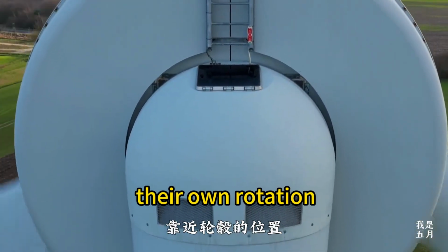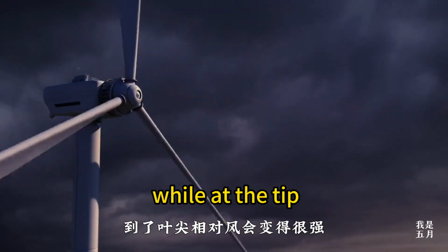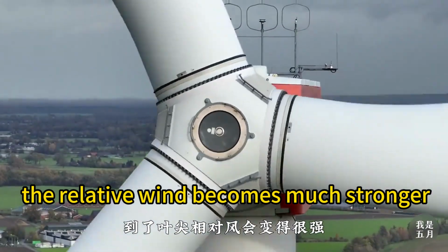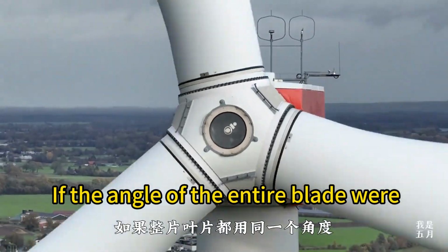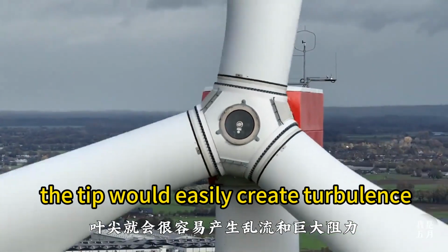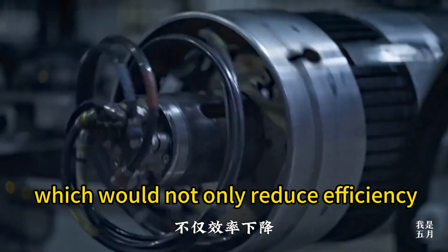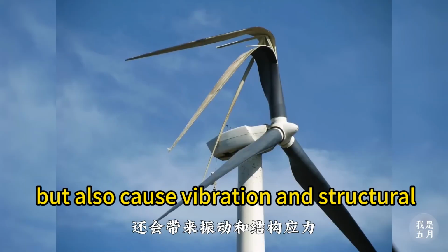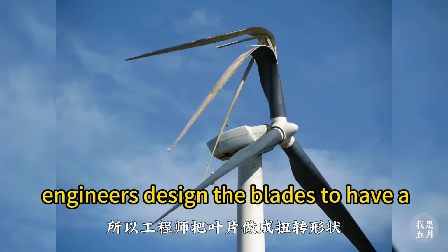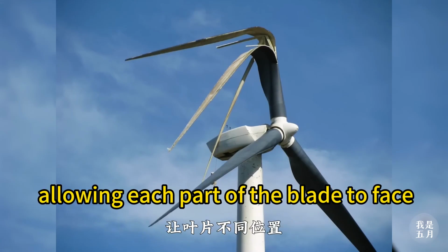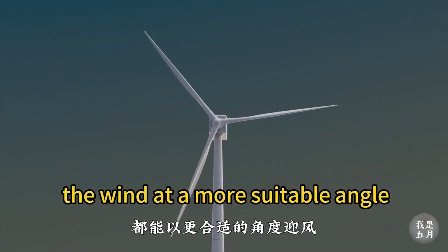their own rotation. Near the hub, the relative wind is smaller, while at the tip, the relative wind becomes much stronger. If the angle of the entire blade were the same, the tip would easily create turbulence and significant drag, which would not only reduce efficiency, but also cause vibration and structural stress. Therefore, engineers design the blades to have a twisted shape, allowing each part of the blade to face the wind at a more suitable angle.